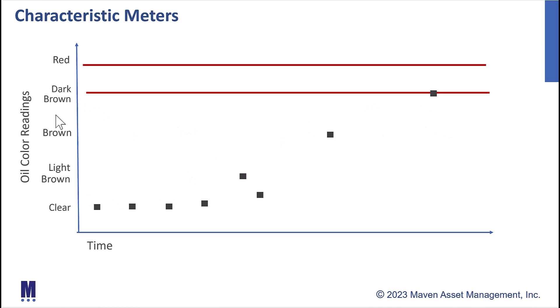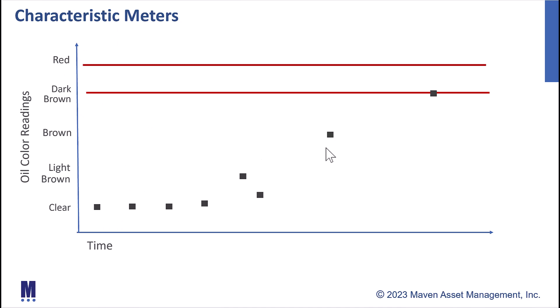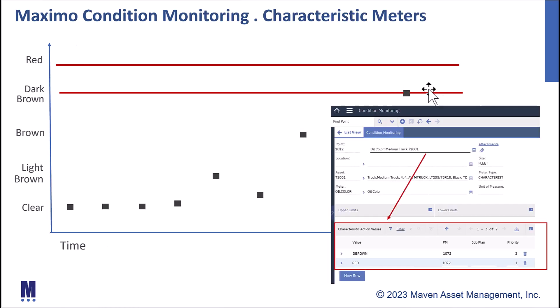But what I can do with my characteristic readings, or what I want to take action on, is if it starts to hit these darker values, maybe a dark brown or a red, I want to take an action. So with our characteristic reading, we see our values over time. Now we start to see them creeping up into some bad colors. It hits dark brown. We want Maximo to automatically generate a PM work order.